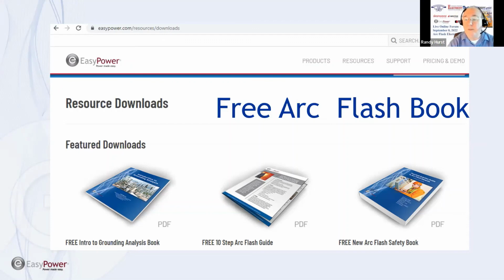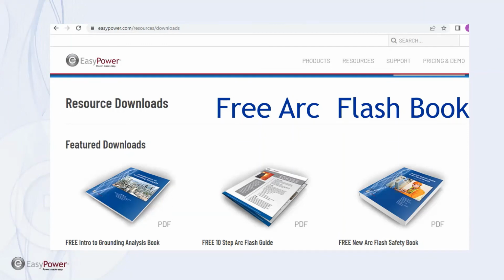Good. The arc flash assessment, somebody mentions this is Carlos, the arc flash assessment should be together with the coordination protection study. So the answer is yes. And if a coordination study has been done and nothing's been changed, in other words, it's a little bit of a gotcha to say, well, we don't need a coordination study. At the very least, you need to spot check to make sure nothing's changed from the original design. So I would agree with Carlos, but that's something that separates a static plant versus a dynamic plant that's had a lot of changes.